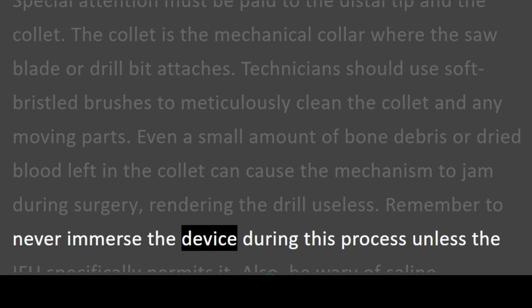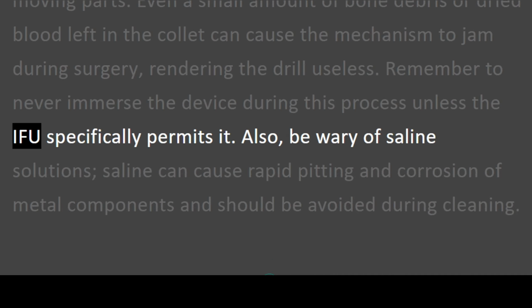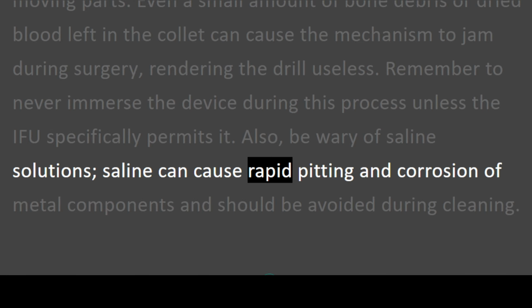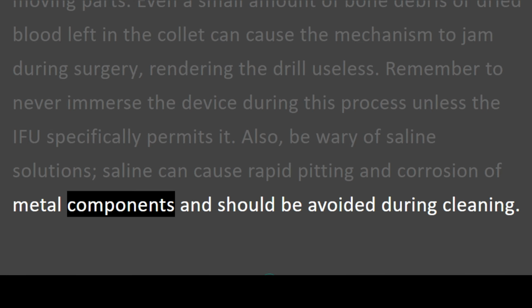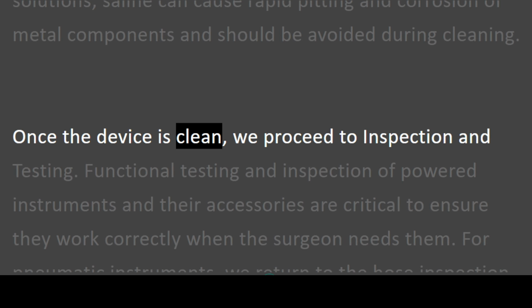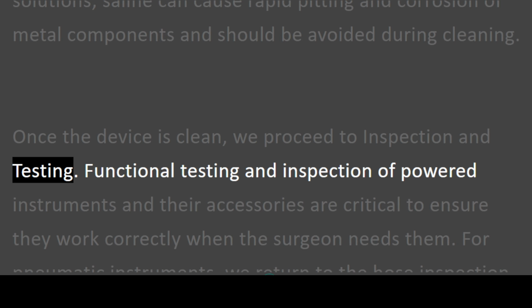Remember to never immerse the device during this process unless the IFU specifically permits it. Also, be wary of saline solutions. Saline can cause rapid pitting and corrosion of metal components and should be avoided during cleaning. Once the device is clean, we proceed to inspection and testing.